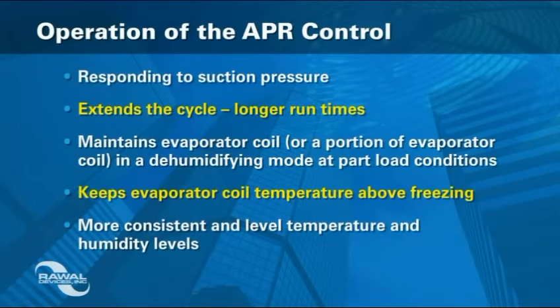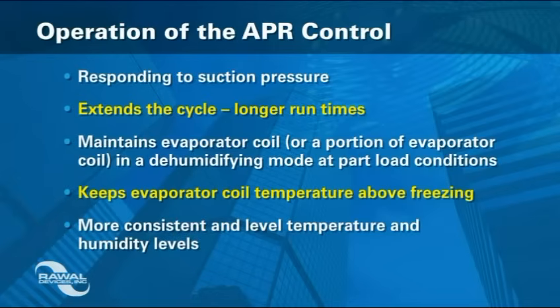Operating on suction pressure assures stable temperature and humidity control without sophisticated electronic controls. The APR Control varies the amount of refrigerant entering the evaporator to match the load conditions, while keeping the active portion of the coil below dew point, thereby continuously dehumidifying.